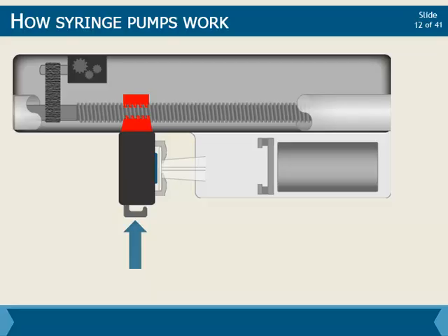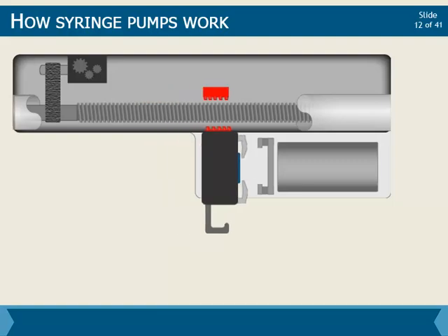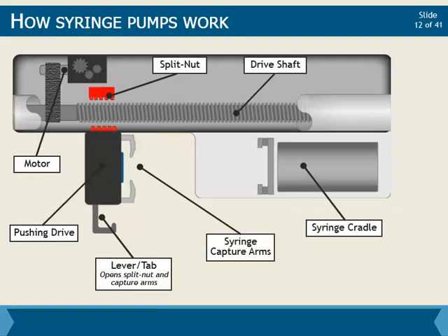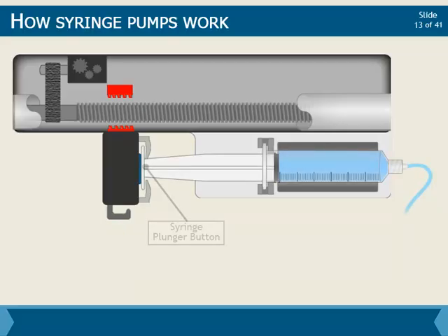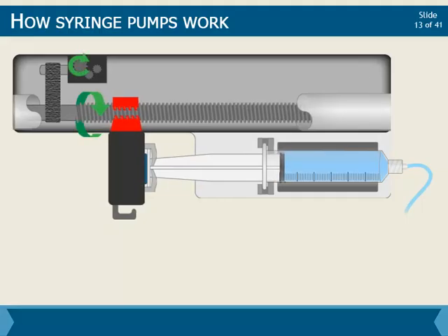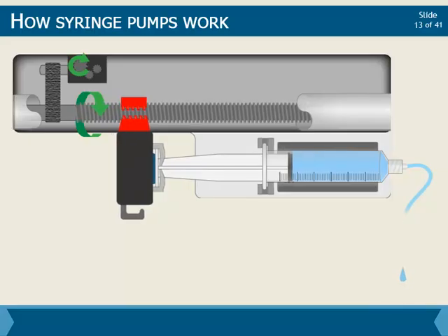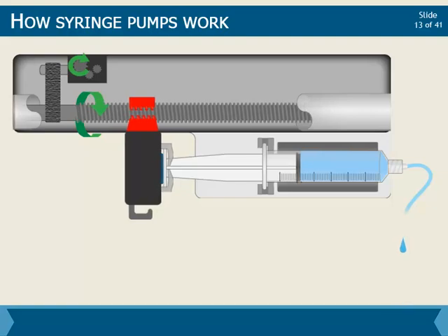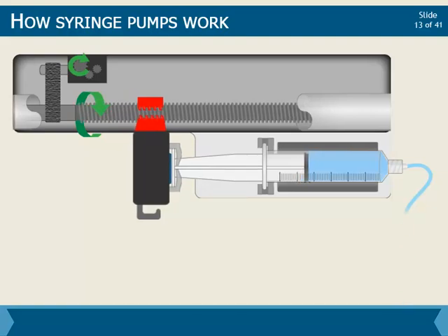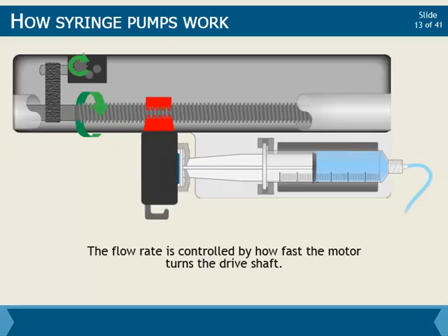There is often a lever or tab that opens the capture arms which hold the syringe plunger button in place. This same lever also opens the split nut and allows the pushing mechanism to move freely up and down along the drive shaft. With the syringe in place, we can release the lever to secure the syringe plunger button within the capture arms. This also allows the red nut to once again lock onto the threaded drive shaft, preventing further movement of the pushing drive by any means except the motor. When the pump is started, the motor rotates the drive shaft and the nut moves downwards along the spinning threads. This in turn moves the pushing drive, which depresses the syringe plunger and forces fluid out of the syringe. The flow rate is controlled by how fast the motor turns the drive shaft.